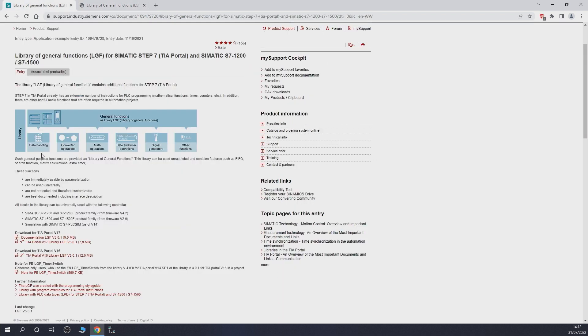The function blocks are contained within this library: data handling, convert operations, math operations, date and time operations, signal generators, and other functions. One very interesting function block I used from this library is the floating average — very, very useful. Basically it's able to collect any form of incoming data — at least 100 samples — and give you an average depending on how many samples you want. Very good function block; it would take me ages to program something like that, but this function block helped me a lot.